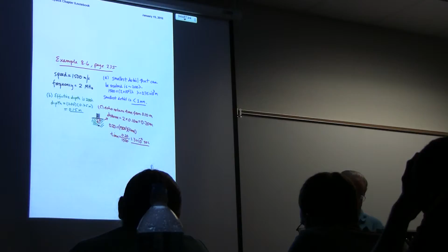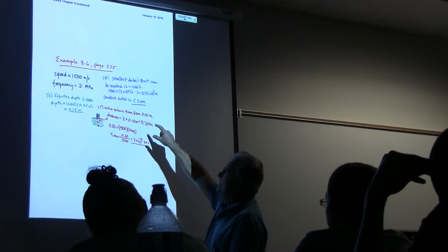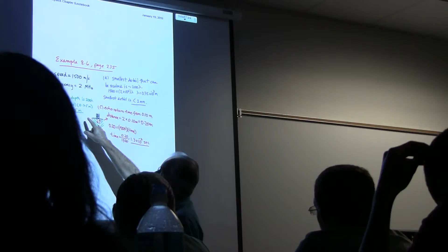They said the speed is the frequency times the wavelength. So the wavelength is going to be the speed divided by the frequency, and you can see you come out with a really, really small number for the wavelength. And so the smallest detail is going to be about that same distance. So that's what I tried to show you up there. The smallest detail is going to be about 1 millimeter that you can see. Rounded, it's about 1 millimeter. How deep did you go? Well, it's going to be 200 times that wavelength. So the depth that it will penetrate is about 0.15 meters, which is 15 centimeters. 15 centimeters is about 6 inches in terms of depth.